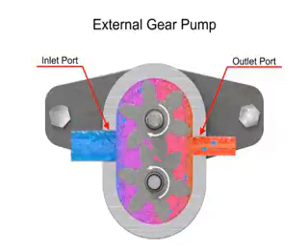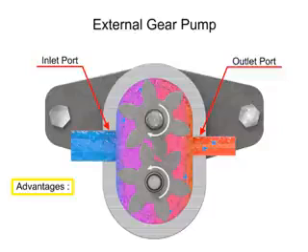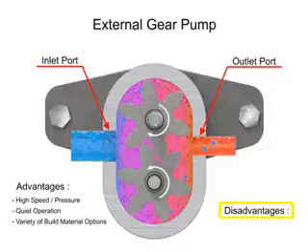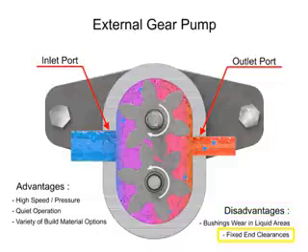The advantages of external gear pumps are their high speed and pressure, relatively quiet operation, and that their design accommodates a wide variety of materials. Disadvantages include bushings in the liquid area that can become worn, and that they have fixed end clearances.